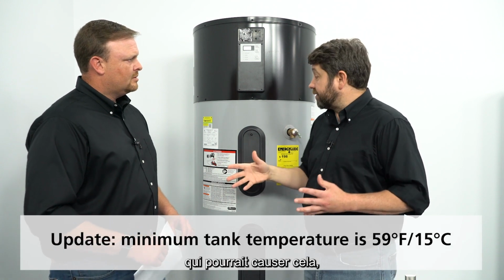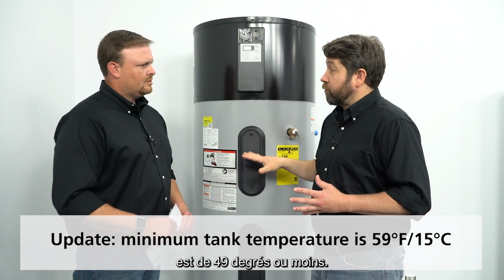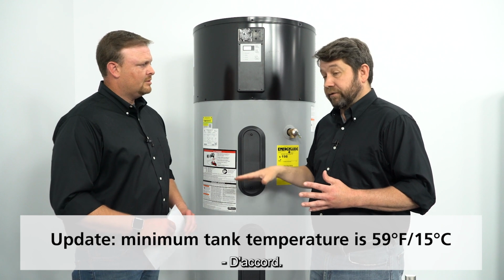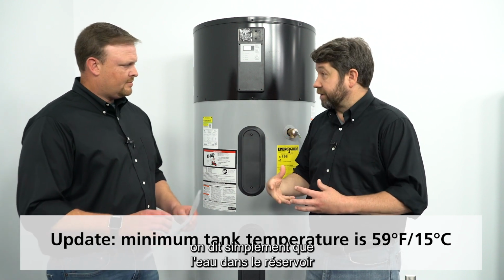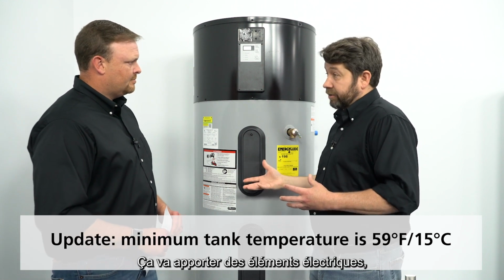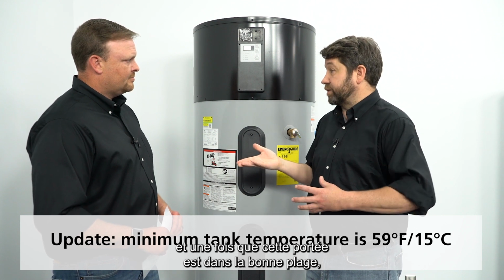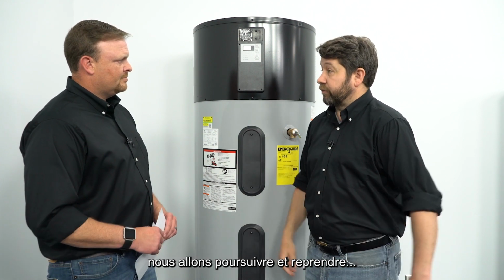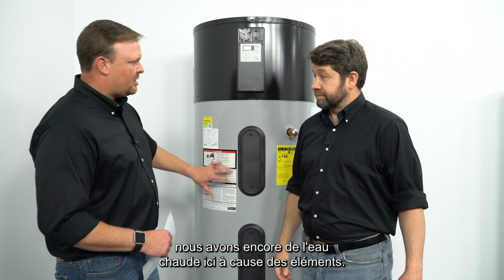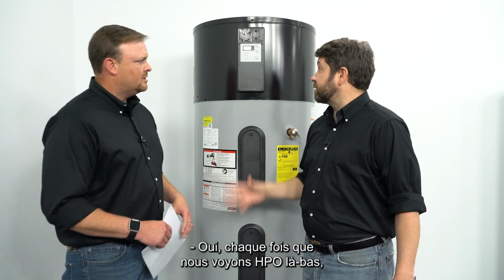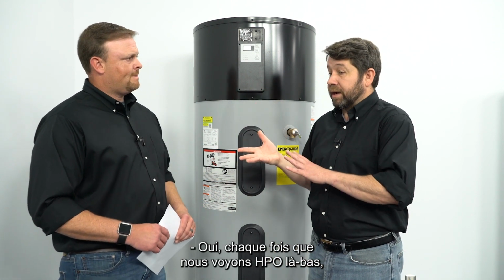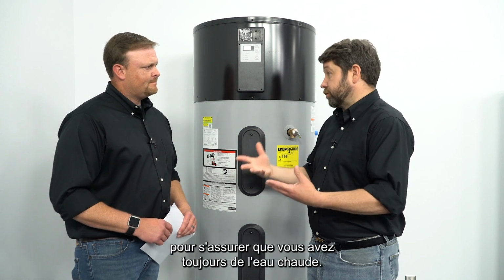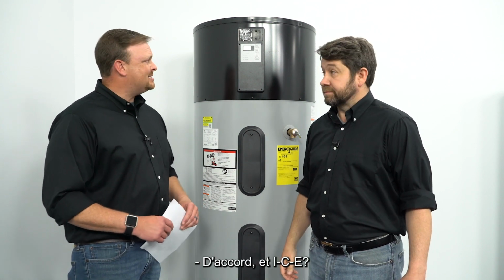Something else that could cause that is if our average tank temperature is 49 degrees or below. So again, it's just saying that the water in the tank may be really cold. It's going to bring the electric elements on. Once that range gets into the correct range, it'll go ahead and resume heat pump, even though you see that we still have hot water because of the elements. Anytime we see HPO on there, it's going to automatically switch to the elements to make sure that you still have hot water. Okay, how about ICE?